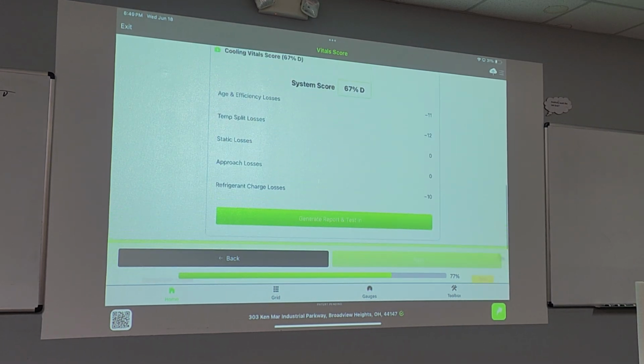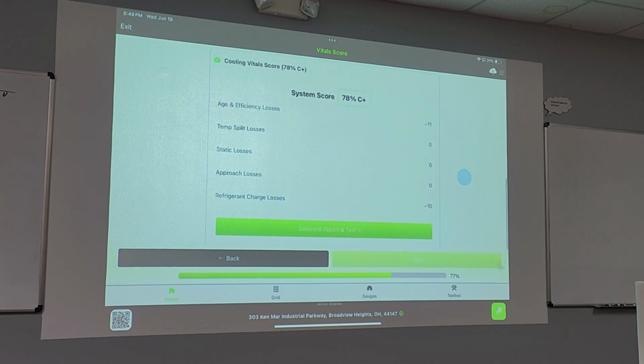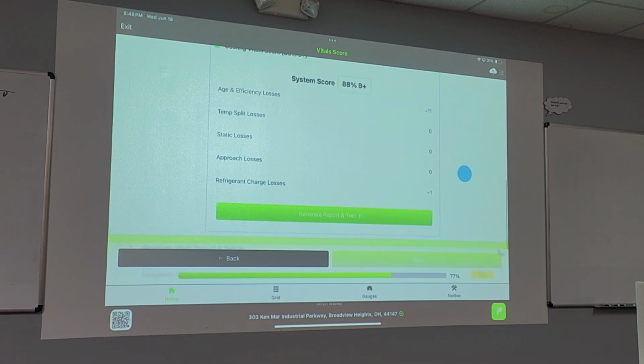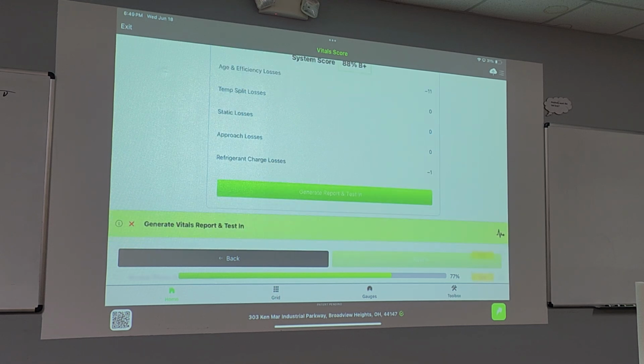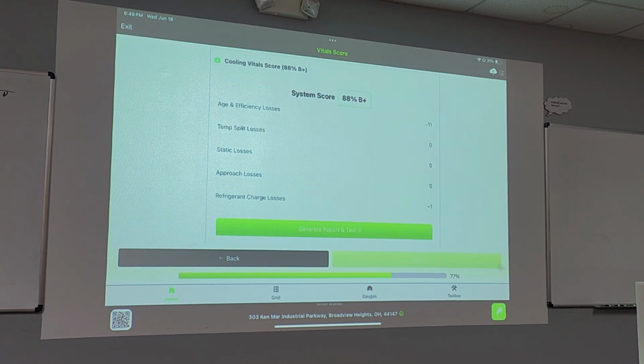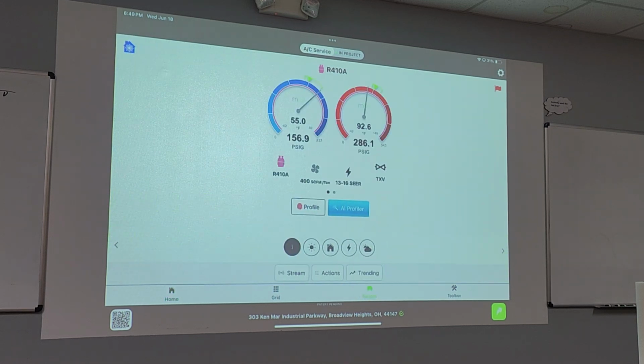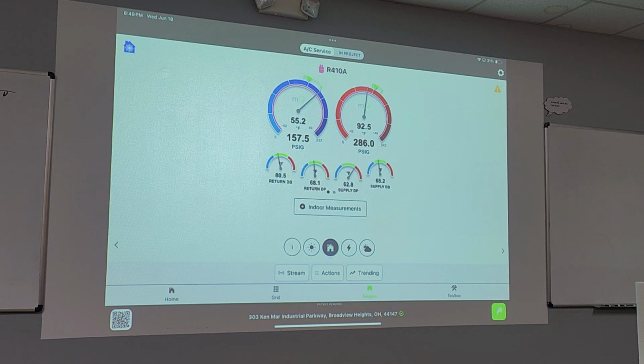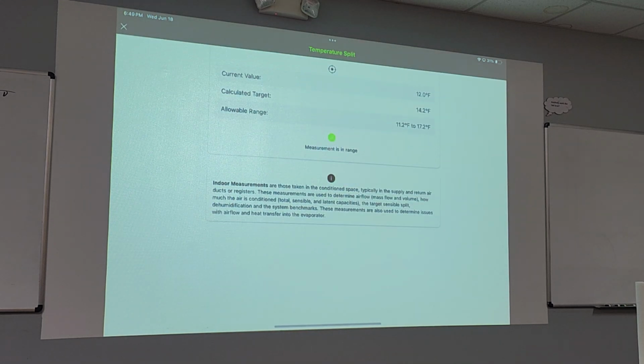When we get into the reports part of this, Phil, you'll see everything in print. Here's another thing, again, situational awareness, right? Right now my temperature split loss is 0, but I just saw it flickering, it was taking like 10 points off for temperature split. So what's the split? Go look at the gauges, what's our split tolerance? Right now my temperature split's 12 degrees, I'm allowed 11.2 to 17.2.